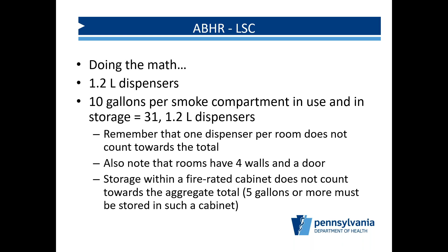I mean, you'd be at the total max, but you would still be at that requirement. And then that's remembering that the 1 dispenser per room does not count towards that 31 total. We said before, rooms have 4 walls and a door, so it's not per exam area where we have just a privacy curtain. And then if you do get over 5 gallons of storage, you have to put that in a fire-rated cabinet. And here's just a picture from NFPA 101 just showing that 1 inch rule. So even if the hand sanitizer is stored 5 feet above the electrical receptacle, we still need to have it 1 inch to the side.